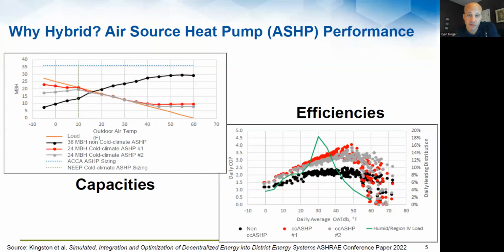The efficiency side of the equation, same 3 heat pumps, by the way, same 3 models. This is outdoor temperature on the bottom. This is coefficient of performance. Coefficient of performance of 1.0 right here, 100% efficient. This is where your electric heater would be. So if it drops below where my red dot is, that would be bad. And by bad, I mean that it would be less efficient than if I just ran straight electric resistance heat, if it drops below that line. So in these guys' case, as you can see, the traditional heat pump, the black one, is obviously not very efficient. It's double the efficiency of electric heat, right? But it is what it is.